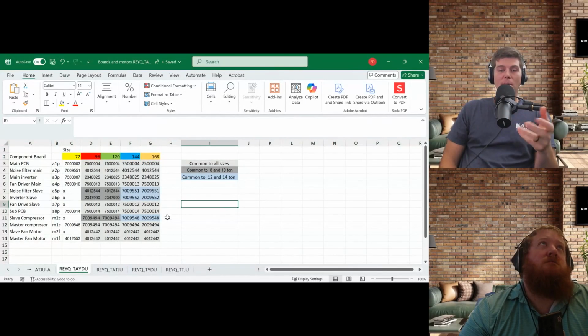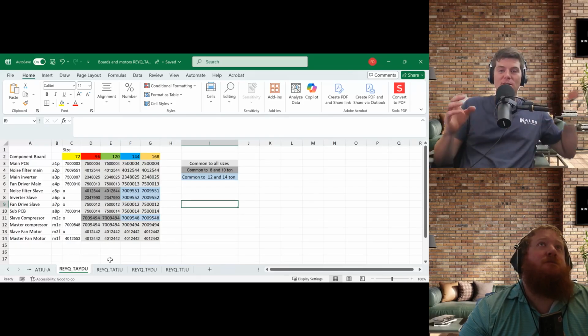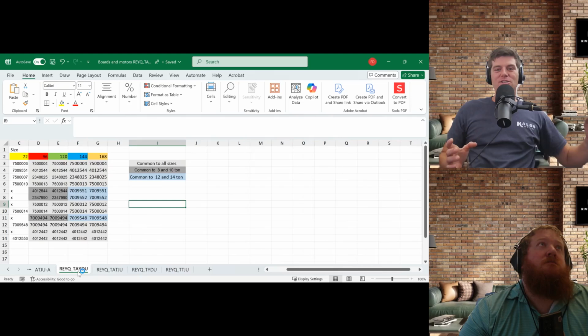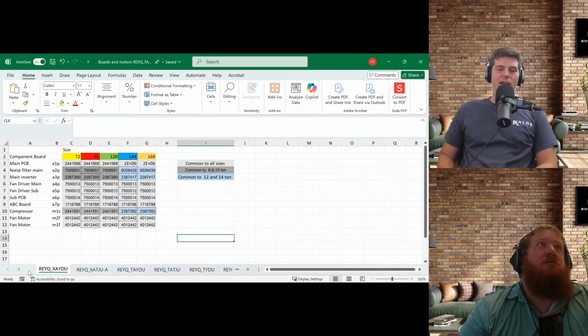And that's the beauty of this - don't go reinvent the wheel. You don't need to memorize what parts go in what units, or what part number each inverter board is for each REMQ model. This stuff already exists somewhere, and what we're trying to show you is how to make your job a little easier by referencing the spare parts bank and building out your own custom spreadsheets if needed. If you're doing enough equipment and replacing enough parts, this is something someone who knows nothing about these products can easily access and triple check, because there's nothing worse than quoting a repair, rolling a technician to the job site, especially two hours away, and showing up to find out you have the wrong parts in hand because nobody knew what the part numbers actually are.